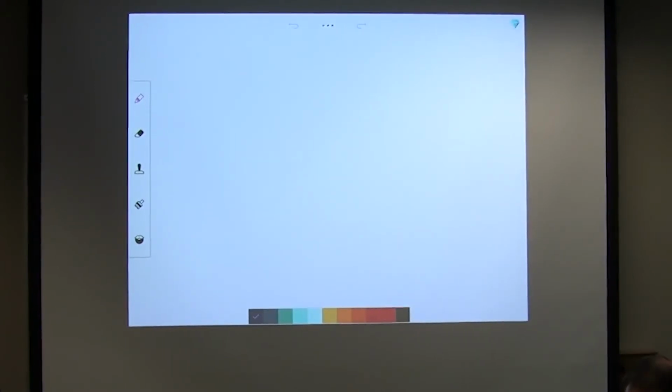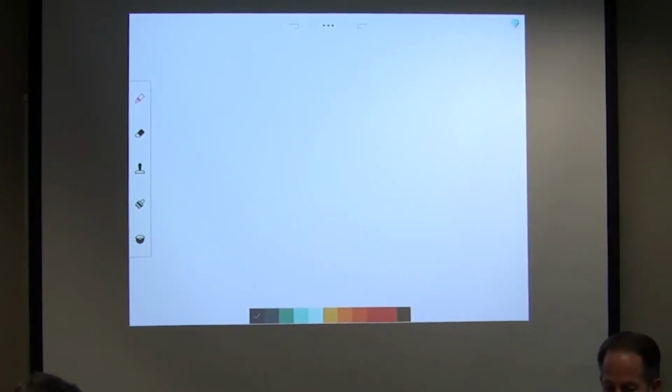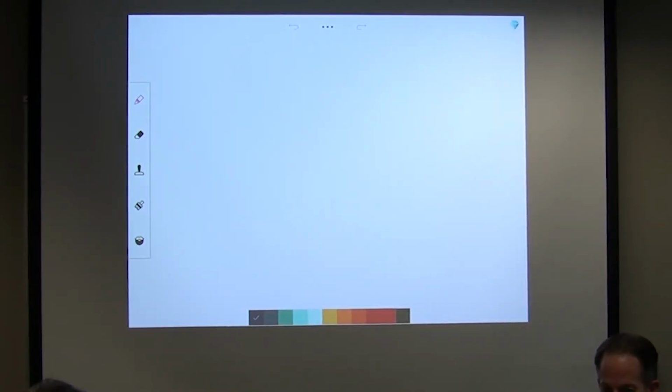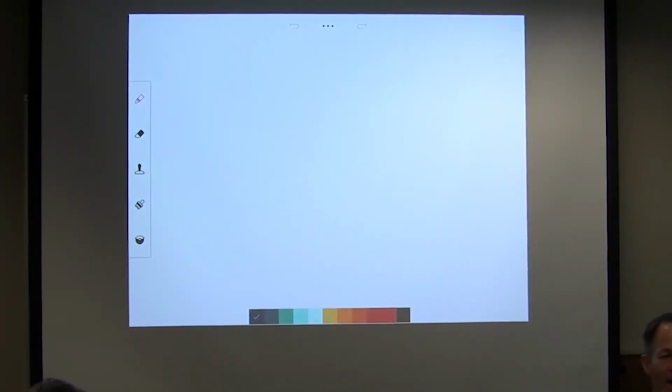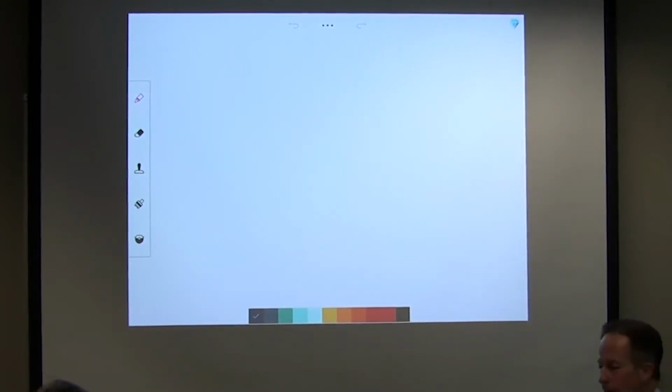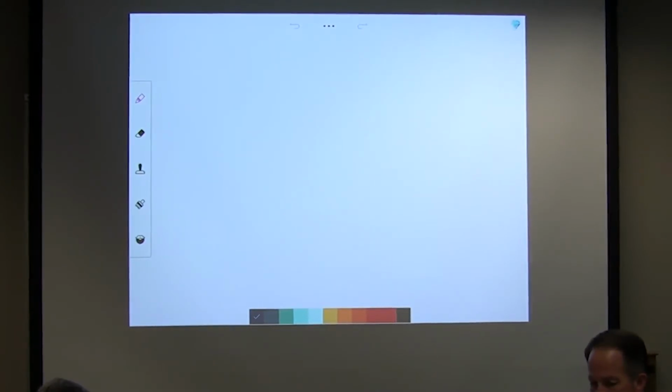It's going to be about 32. 70. No, you can't look. You can tell him the ohms. 70. Scott will be the spokesperson. You've got to look up on your chart. What is 70K? It's like 32 degrees, so around 32 degrees, roughly.